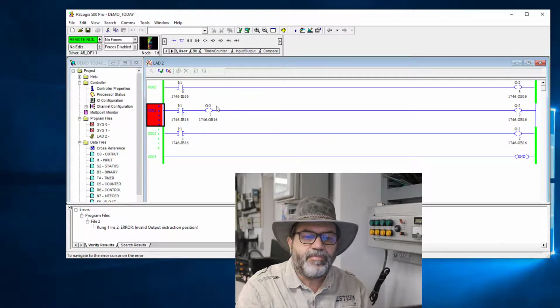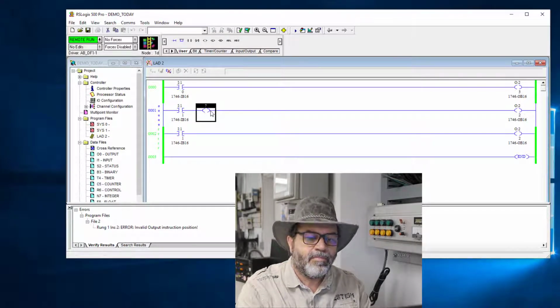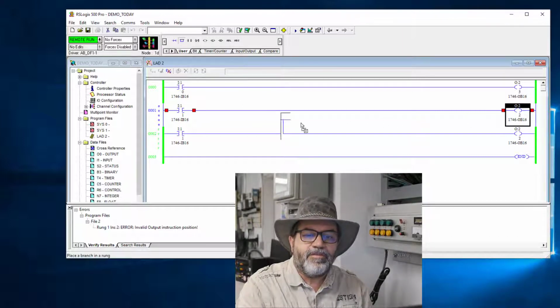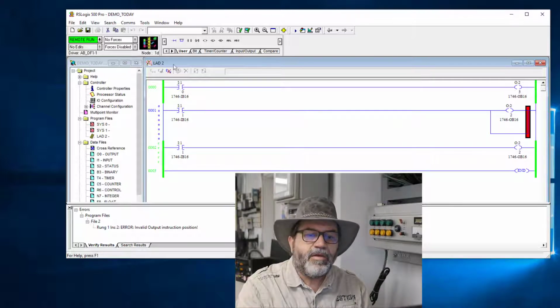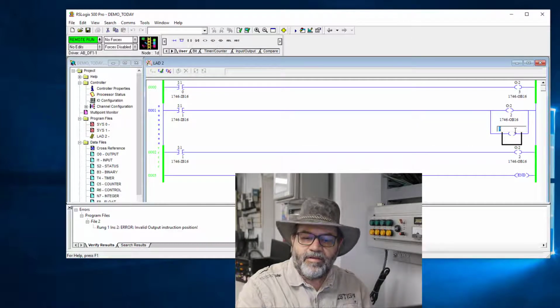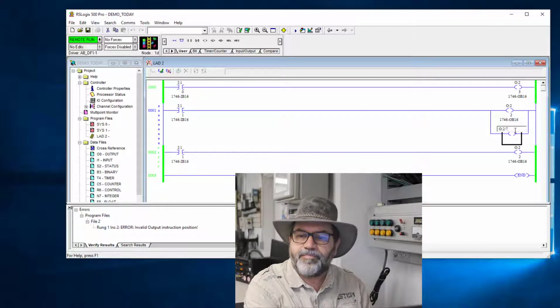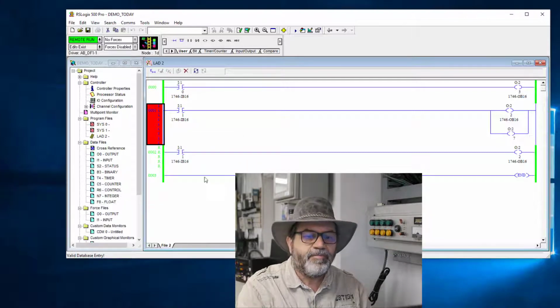And it's got errors. Oh, obviously I'm putting two outputs on one rung, which you can't do. So what I'm going to do is I'll put a branch over here. And I'll see if I can put an output down there. And I think this is going to work. So my output is O:2/7. And hopefully that's happy. So now I'm going to accept my edits, and it accepted.